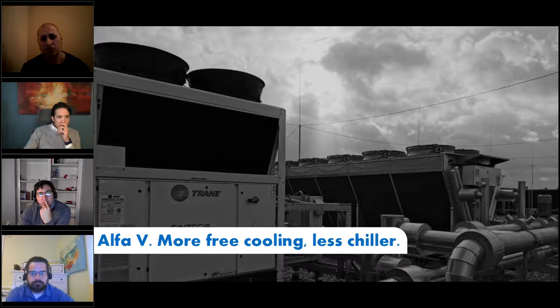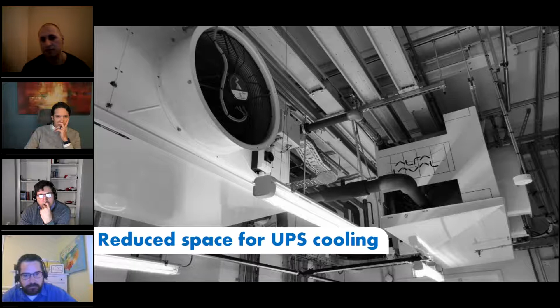They use dry coolers. When we have the possibility to use only free cooling, we use only dry coolers. If they are not enough, we start to cool down after the dry cooler by chiller. And in the hot period, at the peak of the outside temperature, we use just chillers. And also for UPS cooling, it's possible to use such kind of coolers, which are just connected to the top and reduce the space for UPS cooling.